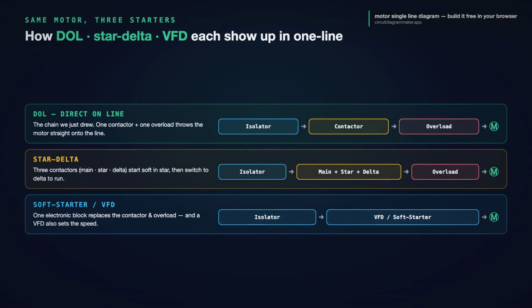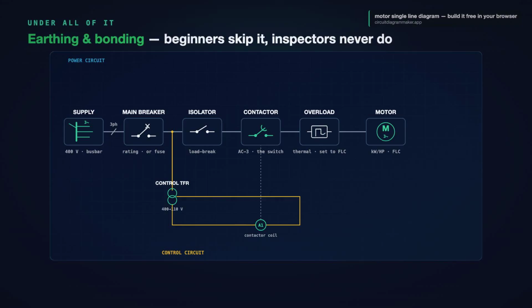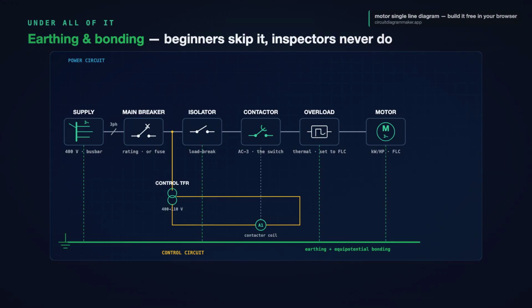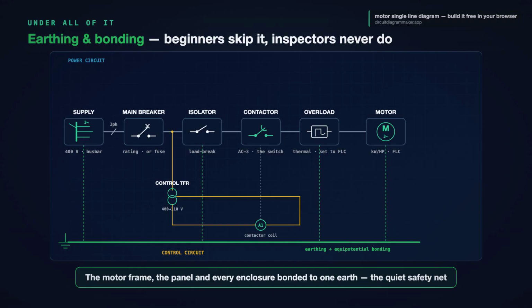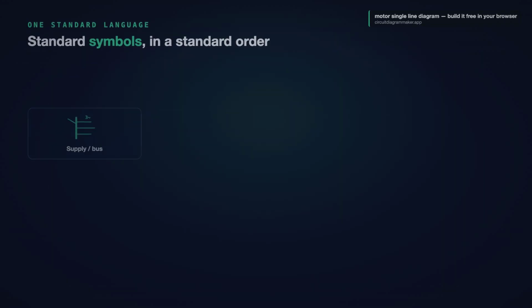And running underneath all of it, earthing and bonding, the part beginners skip and inspectors never do. Every metal part that should never be live gets tied to earth. The motor frame, the starter panel, the isolator enclosure, all bonded together and connected down to the earthing system. On the single line diagram, this shows up as a green earth line reaching every block. Equipotential bonding just means all that metal is held at the same potential, so there is never a dangerous voltage between two things a person might touch at once. It is the quiet safety net under the entire drawing, and on a motor one line, it is not optional. Draw the earth every time, so step back and look at what you have.